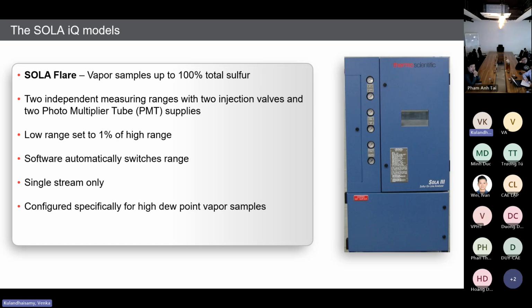The last one is the SOLA flare gas application. The flare gas application can measure up to 100% total sulfur. It has 2 independent measuring ranges, with 2 injection valves and 2 photomultiplier tube assemblies. The low range is set up to 1% of the high range, meaning if your high range is 100%, the low range must be set up to 1%. The software automatically switches the ranges. If you have a dual range, the software will automatically switch the range from high to low.